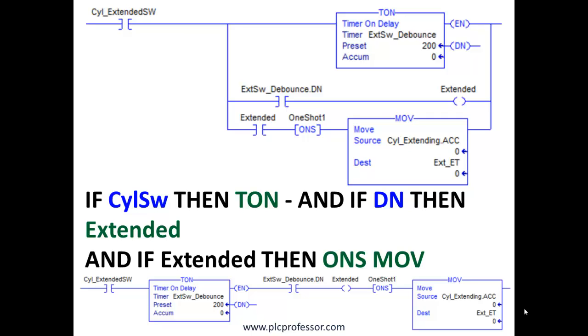The problem with the lower rung is when you look at that electrically, it doesn't make any sense because you're thinking, wait a minute, you can't have a switch, a load, a switch, a load, a switch, a load, and another load all in series because the voltages will divide up and it won't work properly. Well, this is where we're going to deviate from the older way of writing code to this method. Now, when I first saw this, I thought, oh my goodness, somebody's going to do that. But then, one day it was advantageous for me to do it in this form, to keep it simple, and I've been doing it ever since, and I love it. I mean, once you learn to read ladder logic, you'll read the bottom rung much quicker than you'll read the top one.